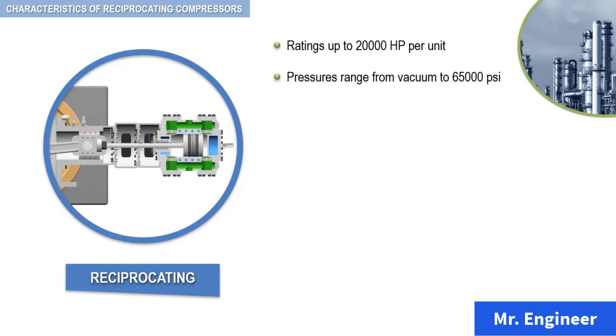The reciprocating compressor is classified as a constant volume variable pressure machine. Why is that? Because it increases the pressure of the gas by operating on the gas in a confined space, a reciprocating compressor will always increase the pressure, provided sufficient power is available and the compressor is designed to meet this objective.